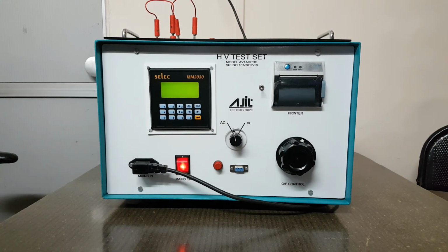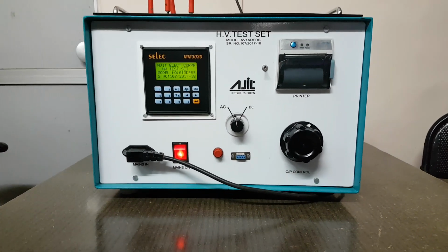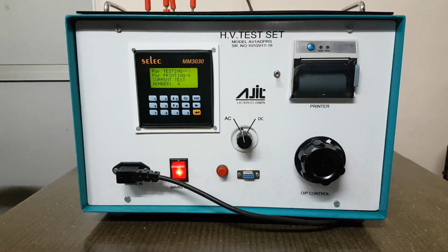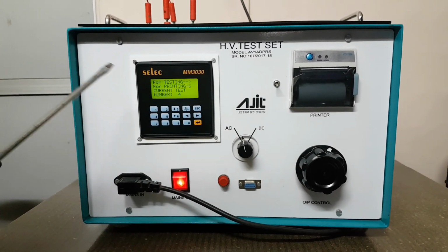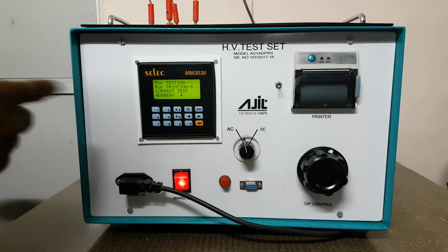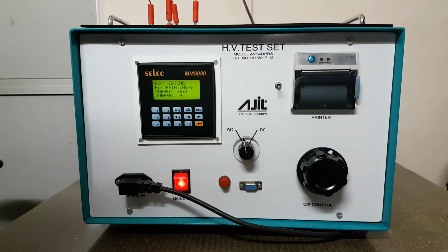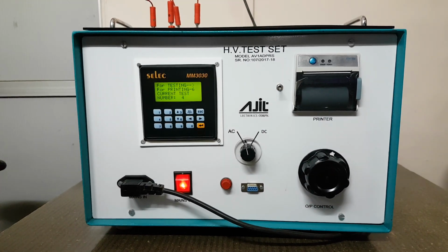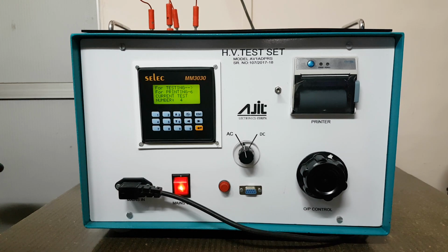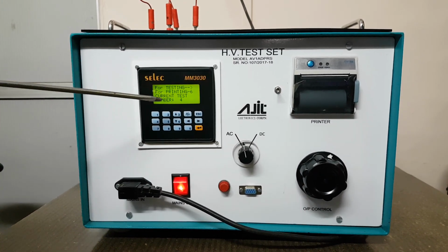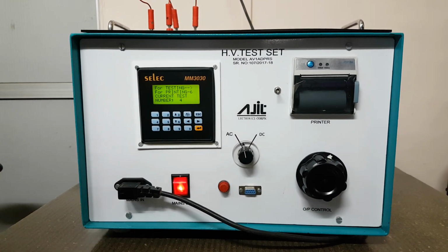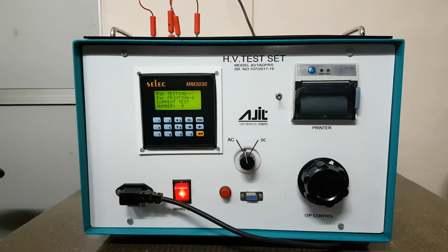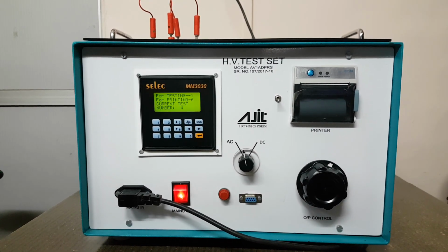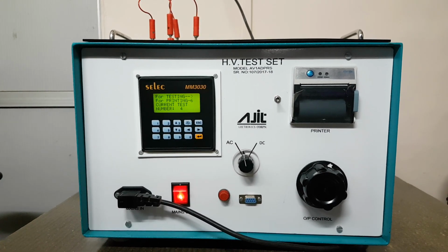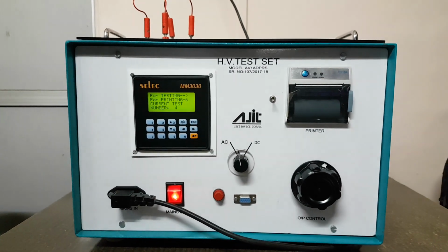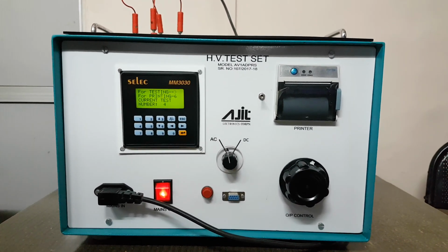Once we switch on the instrument, first the company name, instrument name, model number and serial number will be displayed on the LCD display, and then there are 4 lines. The first line says for testing press right arrow. The past results can also be printed on the printer from here. Then the current test number. Now we will be doing the 4th test, because tests 1, 2 and 3 have already been conducted and stored in the memory of the instrument. So for testing we have to press the right arrow.